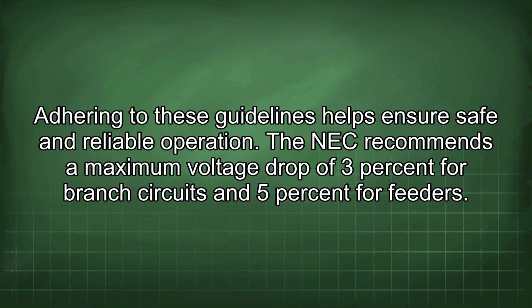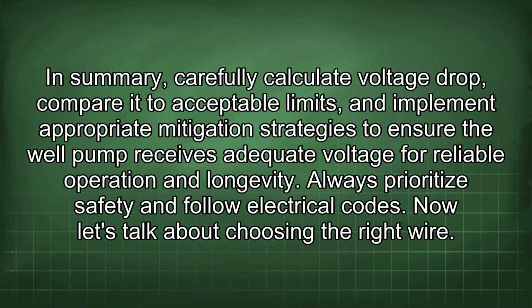The NEC recommends a maximum voltage drop of 3% for branch circuits and 5% for feeders. In summary, carefully calculate voltage drop, compare it to acceptable limits, and implement appropriate mitigation strategies to ensure the well pump receives adequate voltage for reliable operation and longevity. Always prioritize safety and follow electrical codes.